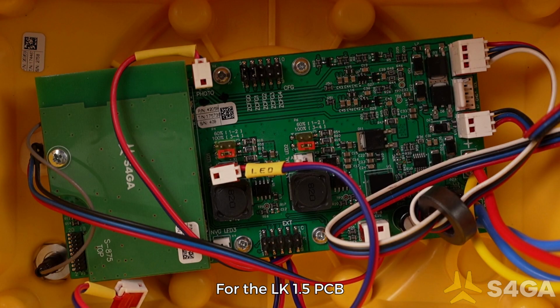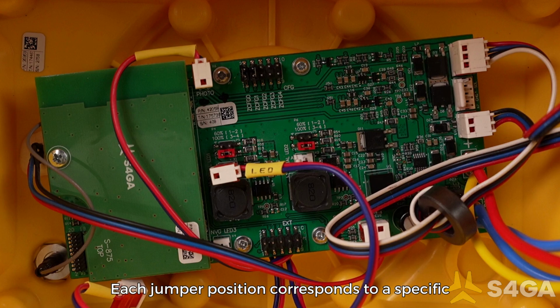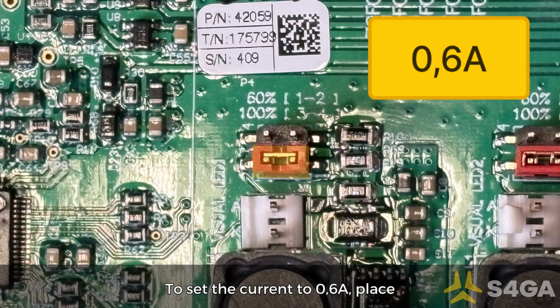For the LK1.5 PCB, the LED current is set using a jumper. Each jumper position corresponds to a specific current level defined by the LED current table. To set the current to 0.6 amperes, place the jumper across pins 3 and 4.